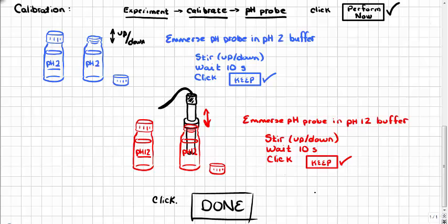Now, once the calibration has been finished, the large display in the background will again become active and it will indicate the pH that the pH probe is measuring. So at this point, it's a pretty good idea to check the calibration. This is easily done by simply taking the pH probe and moving it from the pH 2 buffer to the pH 12 buffer, remembering to rinse in between, and just check to make sure that the pHs indicated on the screen of the computer are reasonably close to 2 and 12 respectively.